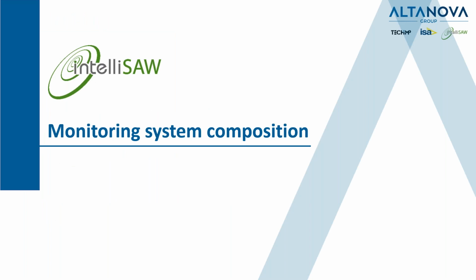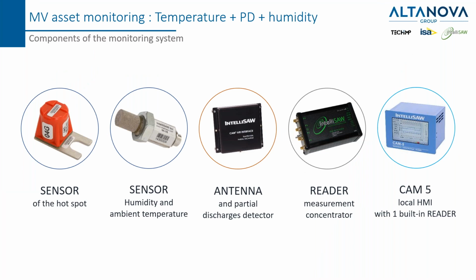Starting from IntelliSaw, we are now having a look at the system composition. The system is basically composed of sensors for the hotspot, a sensor for the humidity and the temperature, because sometimes the failure and the breakdown can be correlated to the environment condition and the hotspot together. There is an antenna that is not only an antenna, but also a partial discharge detector that is operating under the same principle. A reader and a local HMI, which is the brain of the system. You need an antenna in this system composition because the sensors are wireless.